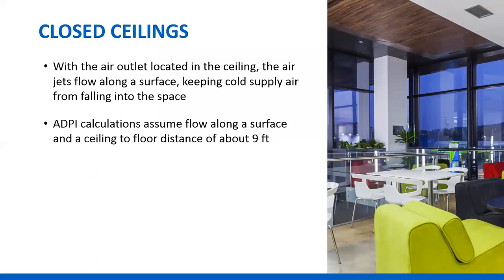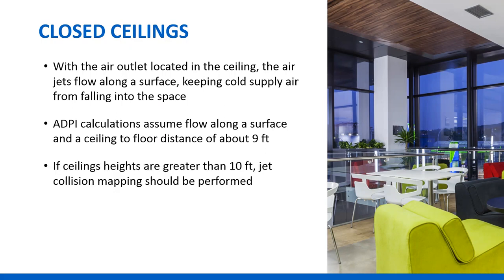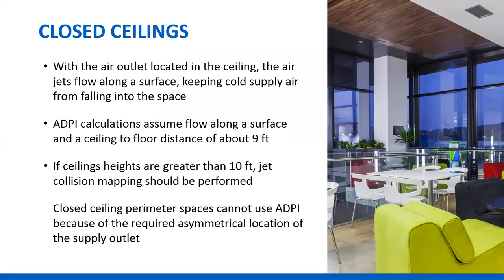When there's a closed ceiling, the throw data from the catalog works because it almost always assumes a surface, and it will keep the cold air from falling into the space. We can use ADPI if the ceiling is around nine feet high — everywhere except in the perimeter. If ceiling heights are greater than 10 feet, we've got to use jet collision mapping. At the perimeter, ADPI doesn't work because the diffuser doesn't have symmetrical airflow — it's offset, and we primarily have to use air jets to figure out what's going on.